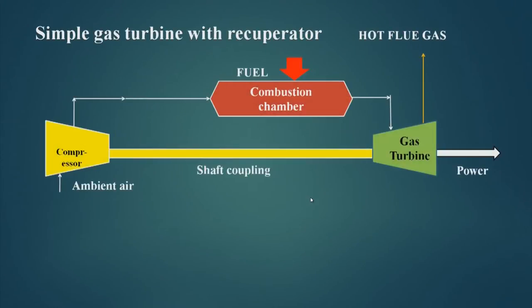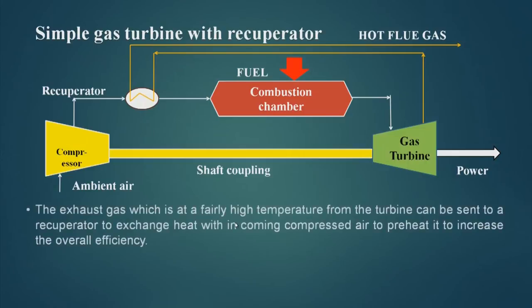There can be a second type of gas turbine which tries to use the hot flue gas temperature to heat the air. In this gas turbine, the flue gas is routed through a recuperator to heat the incoming compressed air. If we heat the incoming compressed air, some heat from the exhaust gas will transfer to the air and thus the fuel consumption will decrease. The exhaust gas from the turbine can be sent to a recuperator to exchange heat with incoming compressed air to preheat it and increase overall efficiency.